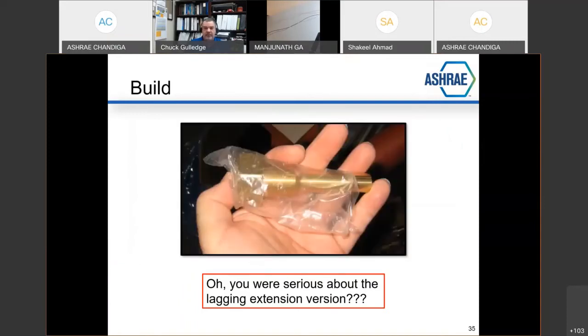Oh, you were serious about the lagging extensions. Okay, remember the conversation I had about minimum insulation thickness? Chill water systems are cold. Hot, humid climates don't like cold, and to avoid condensation, you have to have thicker insulation. When you put this kind of thermowell into the pipe where this part screws into the weld outlet, that's all you've got sticking in, and your insulation projection is out here. I had 100 of these I found that were being installed on a manufacturing facility where somebody cut a corner and didn't put the lagging extensions in so that this part could be outside the insulation. A lot of rework, a lot of waste required to deal with something that had a purpose.